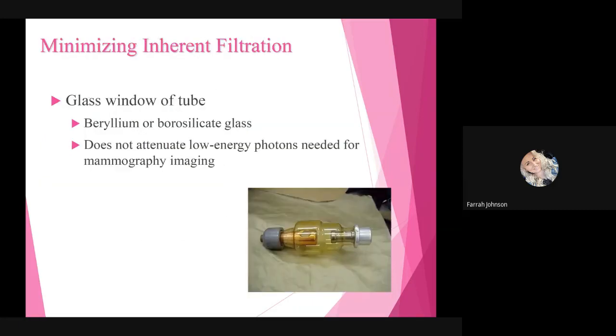So, minimizing inherent filtration, starting with the glass window of the tube. It's typically made of beryllium or borosilicate glass, and it does not attenuate the low energy photons needed for mammography imaging, which is really important because when we are imaging breast tissue, we don't need super high energy photons. You do not want to use a type of glass window that is going to absorb all those very low energy photons that we need. So there's a fine line between absorbing too many or not absorbing enough.